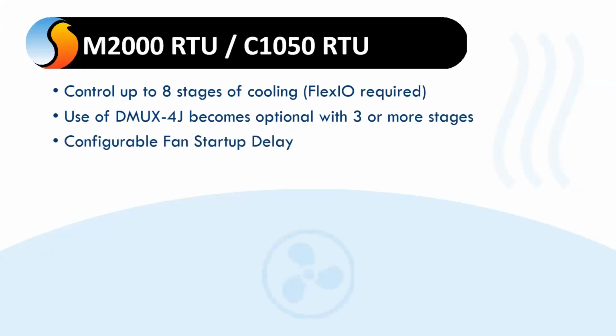We have a configurable fan startup delay. Okay, and this is based off of PowerUp. The intent here is if you have, say, a power loss to the building, so you got 20 package units, it's been hot out, everybody's got a demand, power comes back on, and you have all of your delay timers for your compressors.